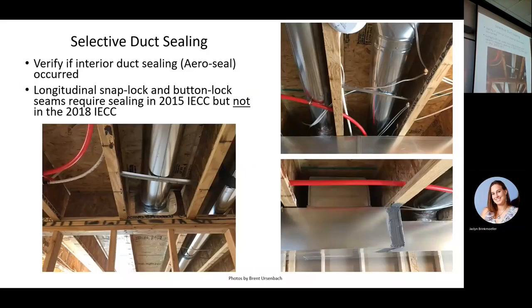But if you're spraying the sealer in the duct, and it's a similar system, you seal the big ones, and then they spray it in, and it's kind of like putting... there's guys with hair the color of mine. Dean, you ever seen people put oatmeal on a radiator to stop the leaks? I've heard of it. Yeah, or leak stop stuff. What's the green slime that you put in a tire that has a leak? It's the same type of process. We're trying to push a sealer into our leaks.